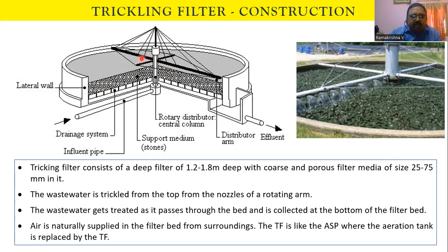They are going to distribute the water. The water is rising, and the rotatory arms are connected with strings to the central column. The water will pass through the rotating arms, and there will be some nozzles, which you can see here. The water will come out from the nozzles.